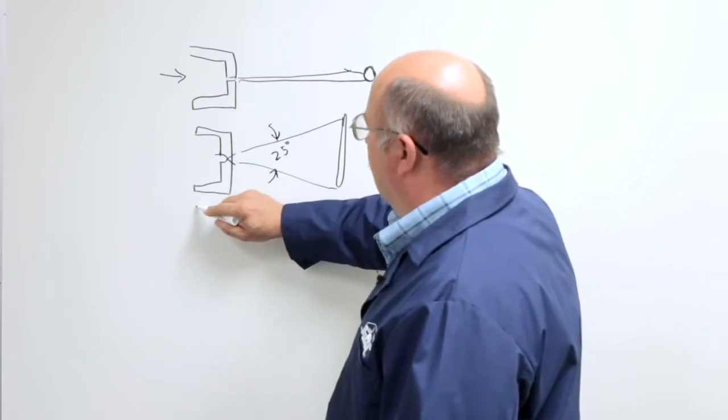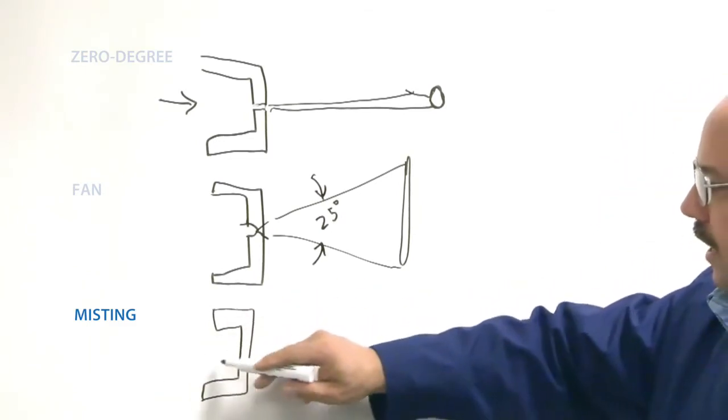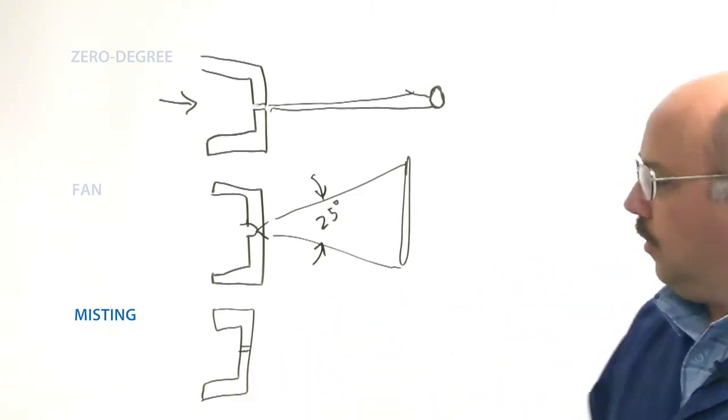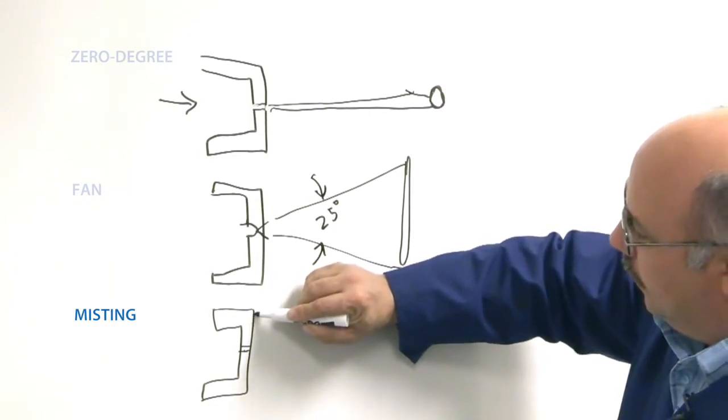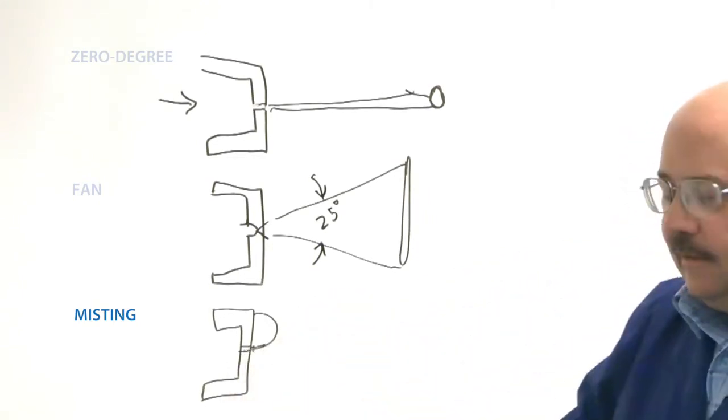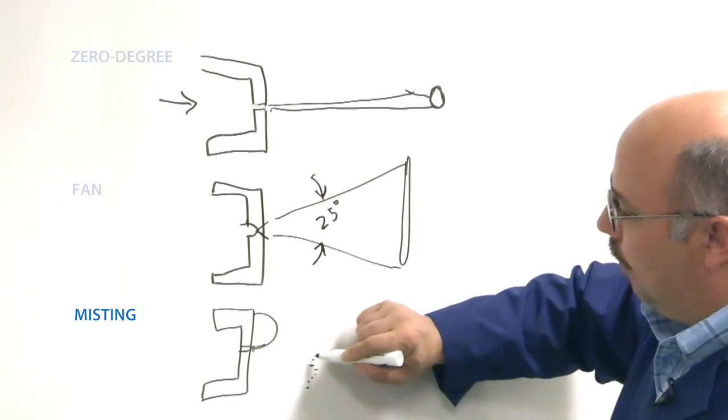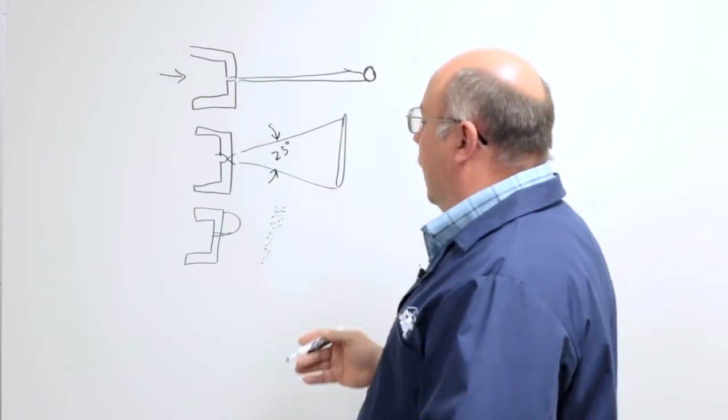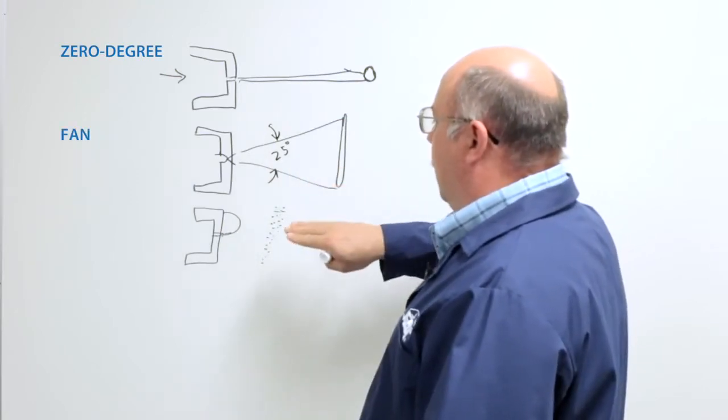The third type of nozzle is a misting nozzle, or sometimes referred to as an impingement nozzle. It starts with the same inner shape with fluid coming in and has a straight hole through it. Usually these are very small in nature. But then there's a small rod that's welded and attached, and the water hits that immediately upon exiting the nozzle. It disperses the water into many thousands of tiny droplets, making a mist or fog. That's used for evaporative cooling and applications like that. So those are your three basic types of nozzles: the zero-degree or direct impact, the fan nozzle, and the misting nozzle.